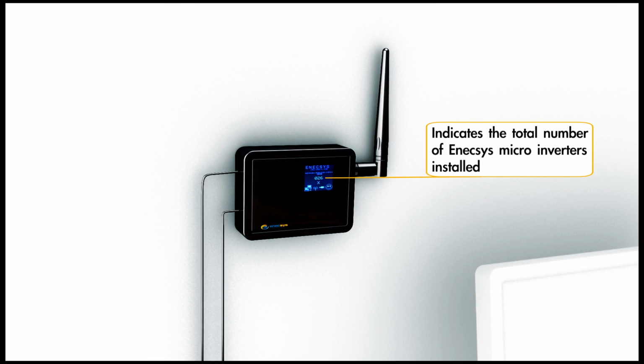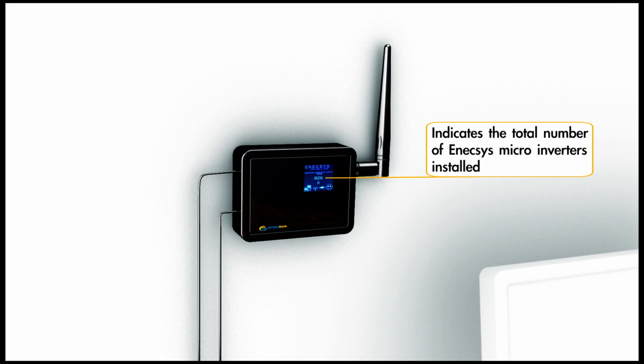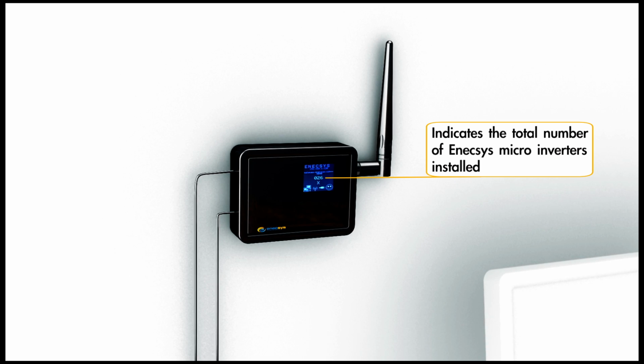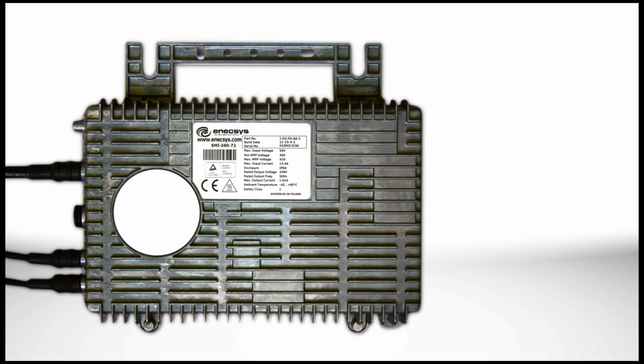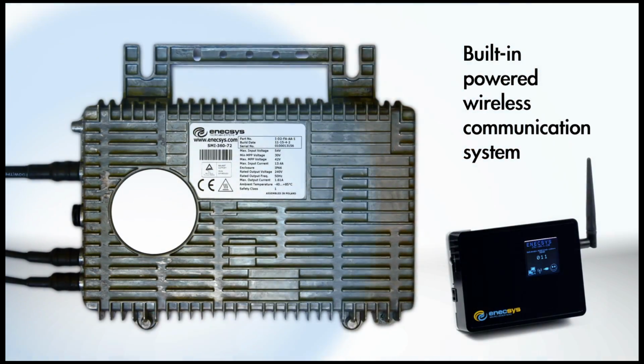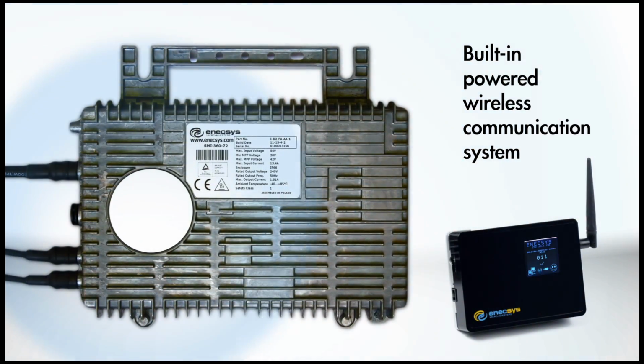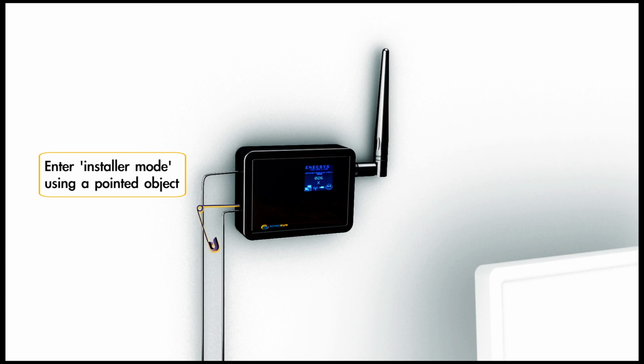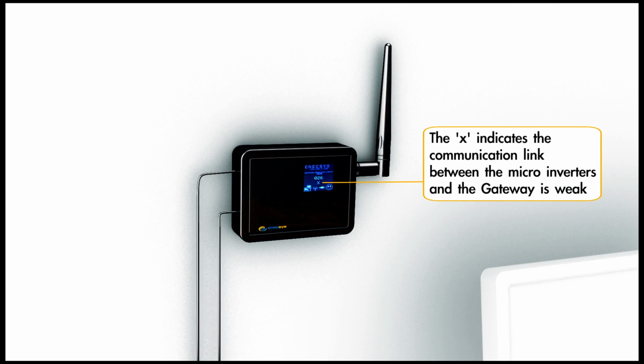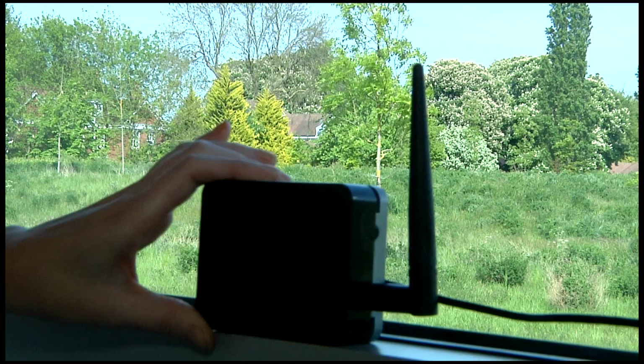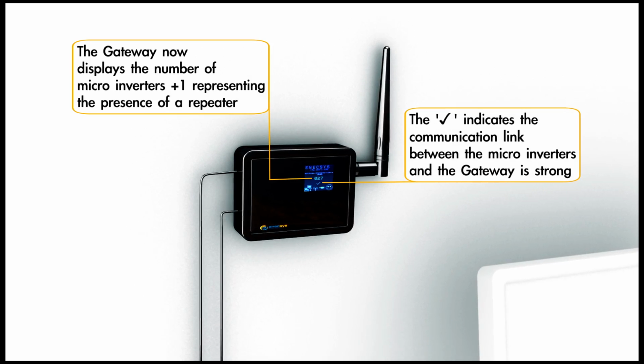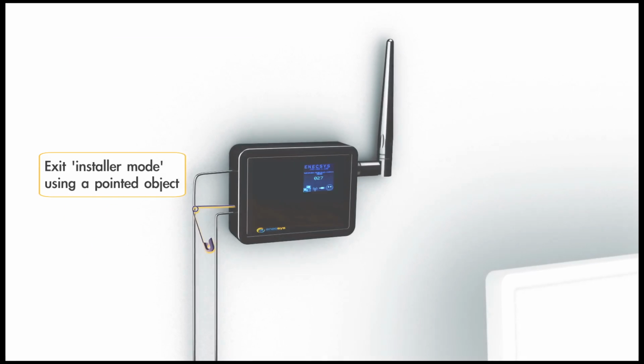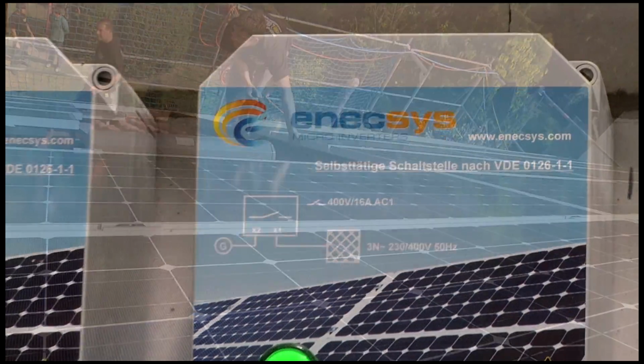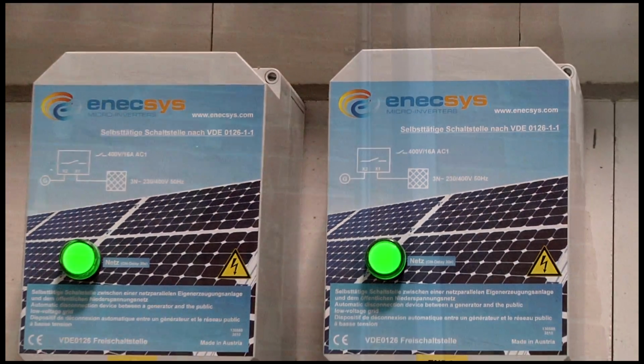Step 4. Check the communication link. Now, check that the gateway displays the total number of microinverters installed. An AC grid connection is not necessary for communication between the microinverters and the gateway. Next, check the strength of the communication link. If the gateway indicates the signal is weak, install a repeater at a location in between the microinverters and the gateway. The Enecsys microinverter system will be connected to the grid according to national requirements.